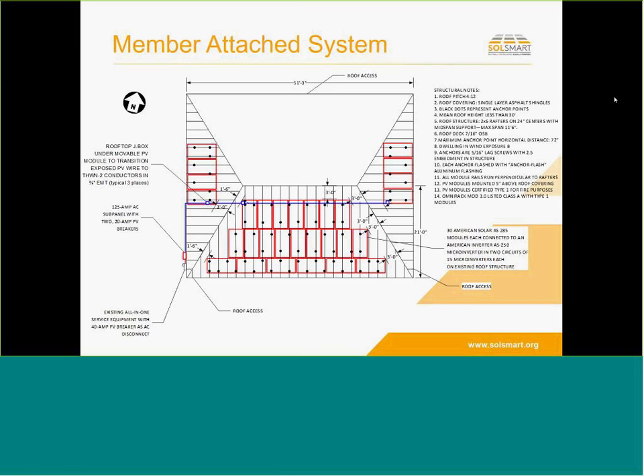When we use the term service in the electrical code, we've got to be careful because services only apply to utility companies. A servicing disconnect, which I think is what you may be thinking about, is to provide ease of service of equipment. If there's equipment on the roof to be serviced, like an inverter, then we are going to have disconnects near it.